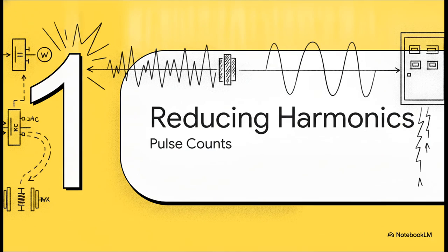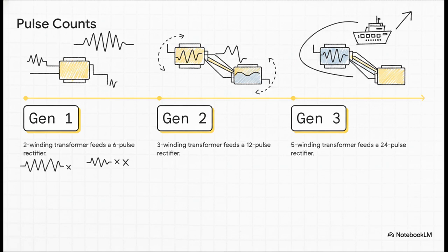Moving right along to our next section, reducing harmonics through pulse counts. First off, it's really worth noting that AC VSDs inherently reduce network harmonics compared to those older thyristor-based DC drive systems. But beyond that, it comes down to pulse counts and liquid-immersed transformers. Looking across these technological eras, a standard setup uses a 2-winding transformer feeding a 6-pulse rectifier. It works, but it gives you the roughest waveform.